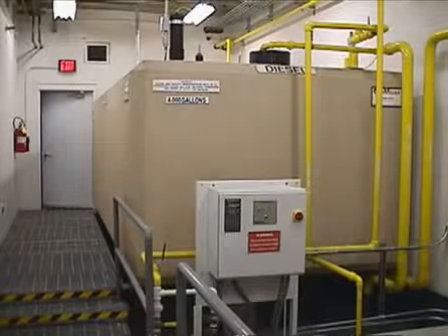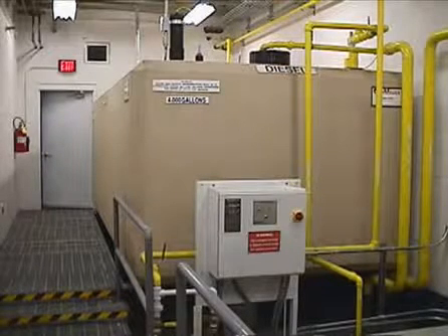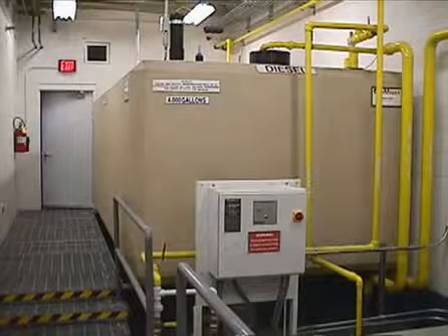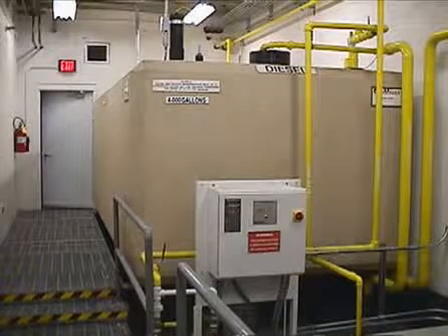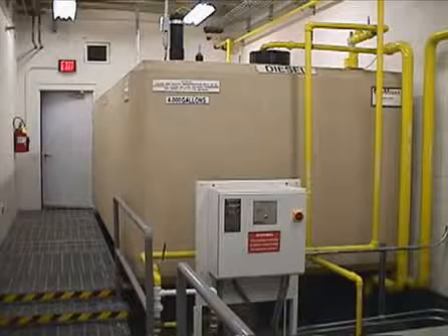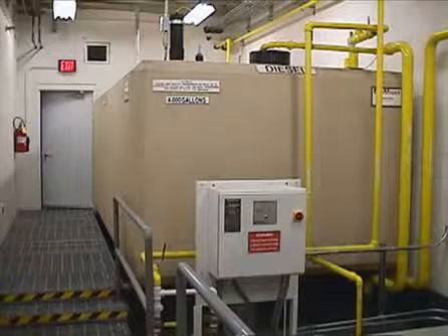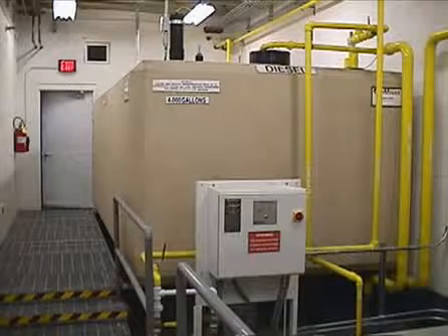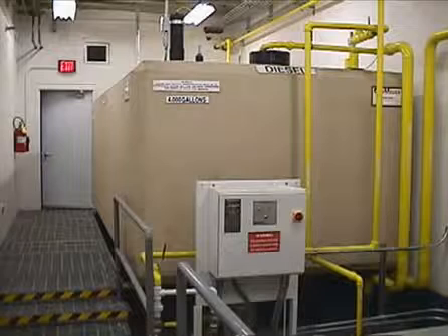Some of the important coordination issues are: the tank rooms are typically fire-rated construction with dikes or curbs to contain leaks or spills within the room. Access and exit from the room needs to be planned carefully. The tank rooms may have special requirements for dedicated ventilation with special requirements for fire conditions. Also, pipe routing through the building, especially riser space, needs to be coordinated.